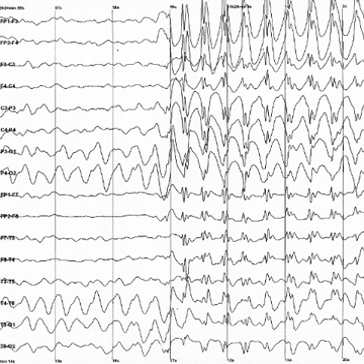Motion artifacts introduce signal noise that can mask the neural signal of interest. Therefore, effective signal noise processing measures were of great interest in the scientific community. An EEG-equipped phantom head can be placed on a motion platform and moved in a sinusoidal fashion. This contraption enabled researchers to study the effectiveness of motion artifact removal algorithms. Using the same model of phantom head and motion platform, it was determined that cable sway was a major attributor to motion artifacts. However, increasing the surface area of the electrode had a small but significant effect on reducing the artifact. This research was sponsored by the U.S. Army Research Laboratory as a part of the Cognition and Neuroergonomics Collaborative Technical Alliance.